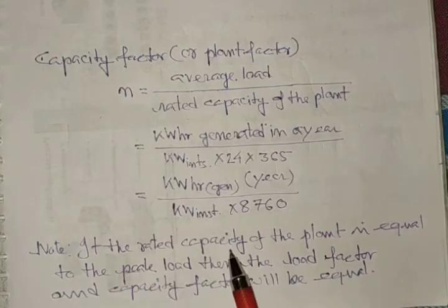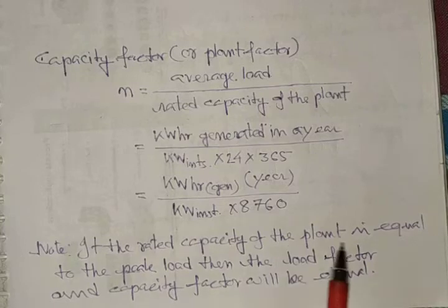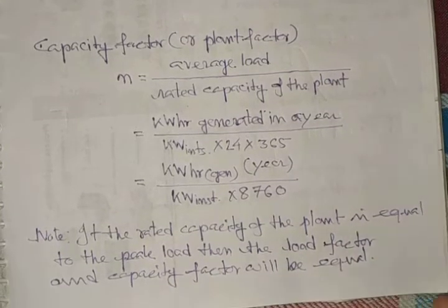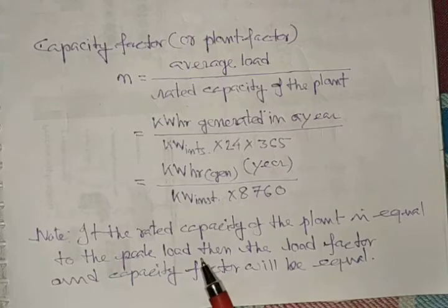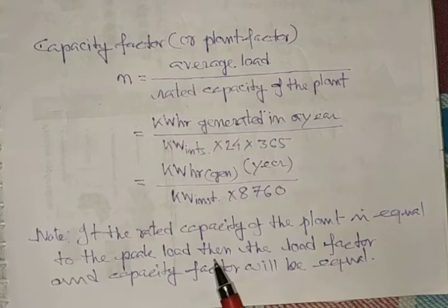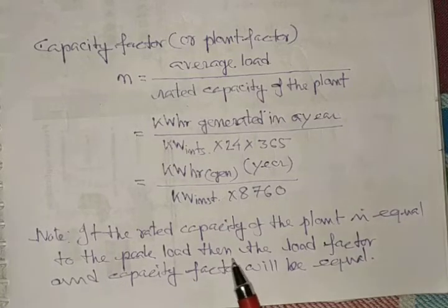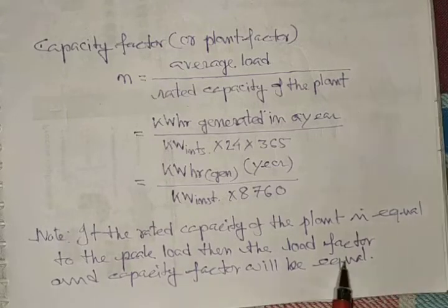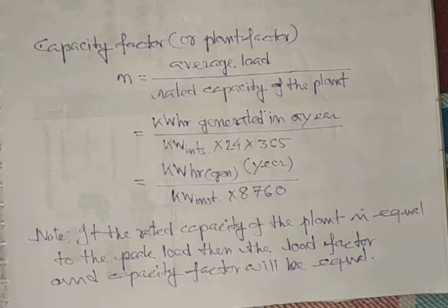If the rated capacity of the plant is equal to the peak load, then load factor and capacity factor will be equal. So they are numerically equal if the capacity of the plant is equal to the peak load of that particular distribution of the energy.